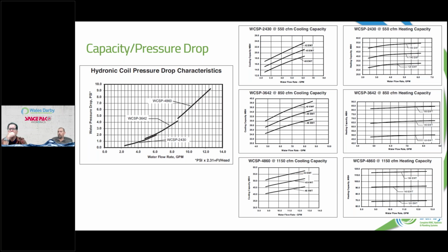We're using one circulator to do it, and I want to say it was the VT circulator, the Delta T. And we had 2 air handlers, so when the zone valves opened, water could have gone down the path of least resistance, right? The one right next to us in a mechanical room instead of the one up in the attic. So the GPMs were off, but we didn't know what they were.